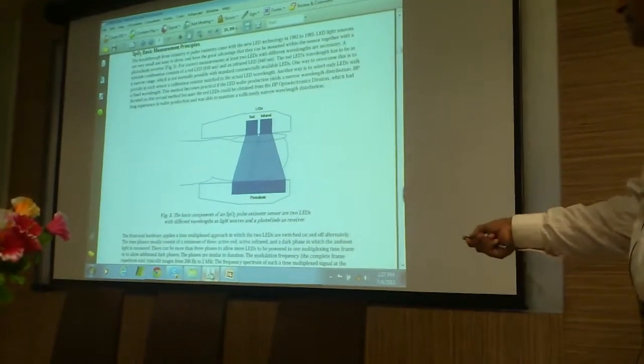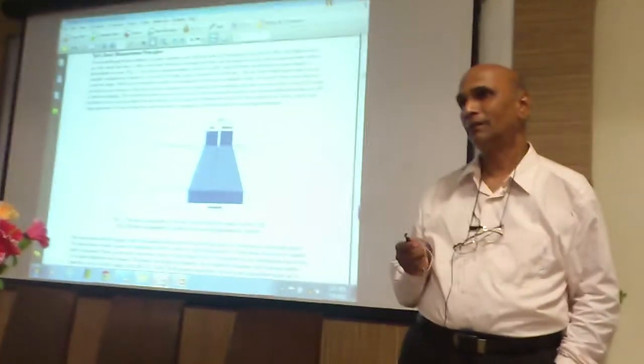This is a new family of sensors from HP's biomedical instruments division. Here they show the probe with red and infrared light on the top — this is a clip, there is a wide area photodiode below, and this is a finger with a nail. Obviously if there is nail polish on it, this will not work. That's why nail polish must be removed before using a pulse oximeter. The red light passes through the blood, the infrared also passes through the blood and is detected on the photodiode. But remember — only one light at a time: either red, infrared, or none (ambient).